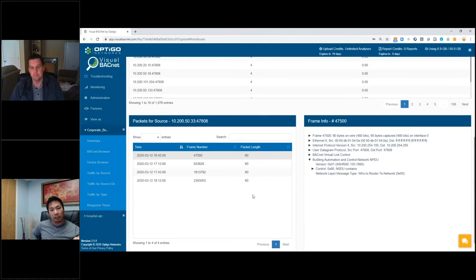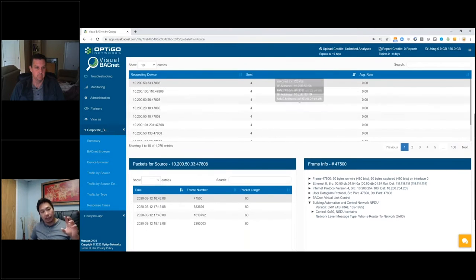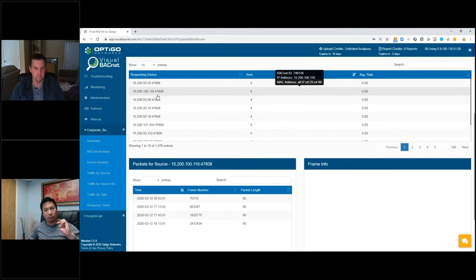And by the way, what this tells me is that this is not triggered by a human, right? So it's not an operator going out there and saying, hey, I'm doing a discovery. I want to find out everything. I'm trying to create a database of some sort. This is programmed in. You can tell it's exactly every 30 minutes. So clearly it's in the programming, these devices every 30 minutes. We can look at other ones, but you can see that this is every 30 minutes. So right away it tells you it's not a human operation, right?